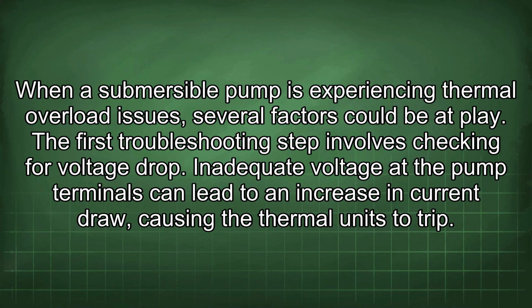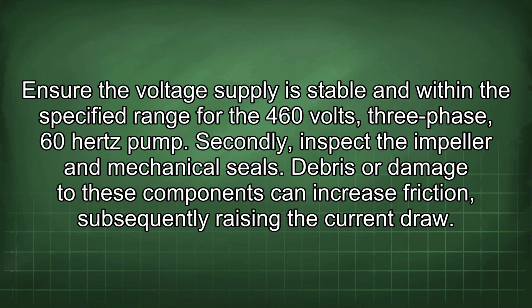When a submersible pump is experiencing thermal overload issues, several factors could be at play. The first troubleshooting step involves checking for voltage drop. Inadequate voltage at the pump terminals can lead to an increase in current draw, causing the thermal units to trip. Ensure the voltage supply is stable and within the specified range for the 460 volts, 3-phase, 60 Hz pump.